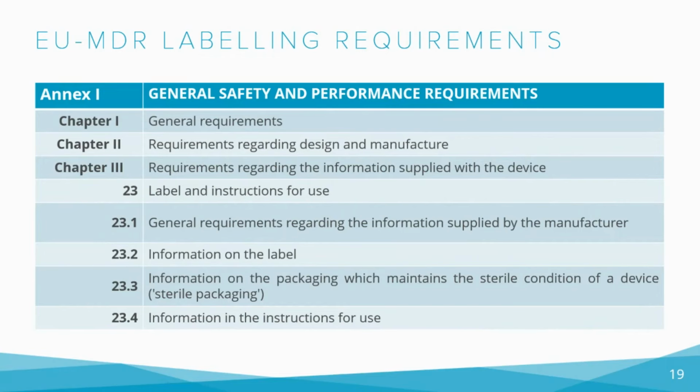Let's see in brief. In part one, there are five key points that the manufacturer needs to follow. Firstly, easy-to-understand labels. That is to say, the contents of the label shall be easily understood by the user of the device. Secondly, the information required on the label shall be provided on the device itself. If not practicable, then the information to users shall be available on all levels of labels as practicable. Thirdly, labels shall be in human-readable and machine-readable format, for example RFIDs or electronic formats, that is to say electronic IFU, eIFU, or non-paper format.